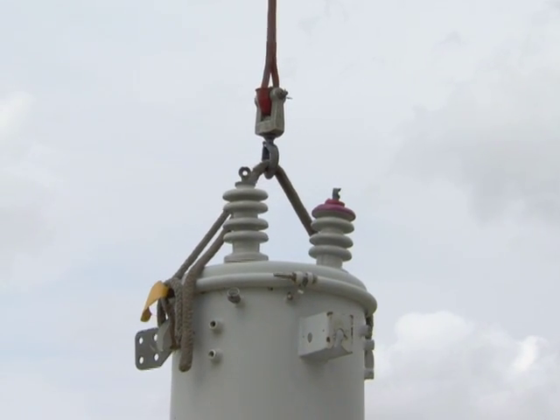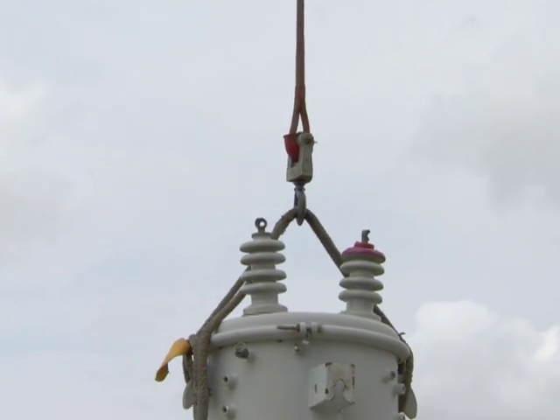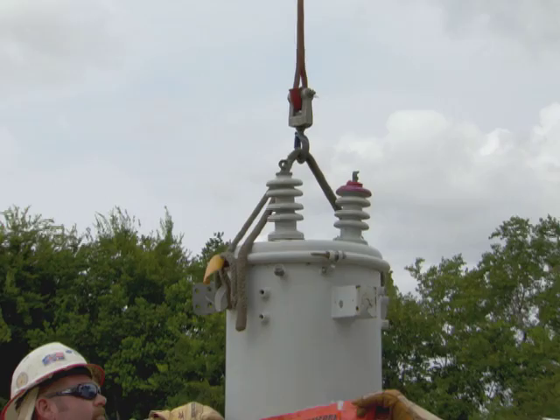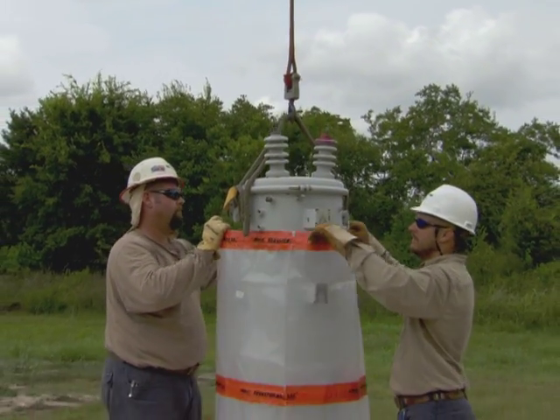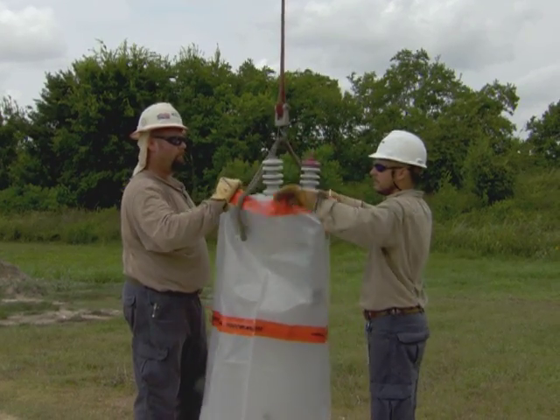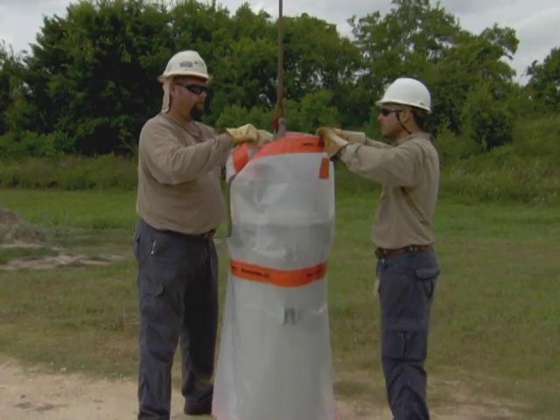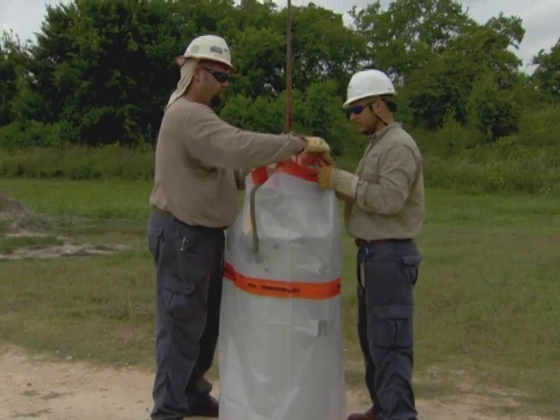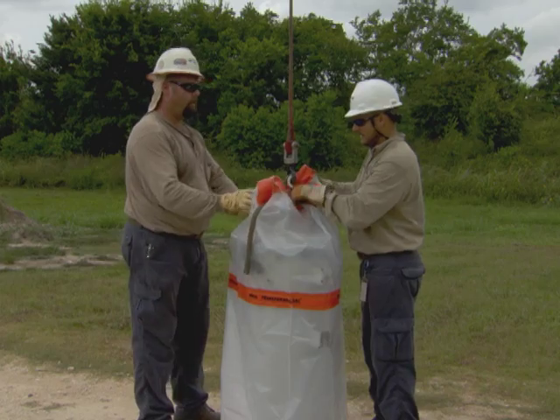Even though CenterPoint Energy, with your help, is working diligently to restore power as quickly as possible, our responsibility to the environment will not be compromised. Oil spills resulting from leaking or damaged transformers, hydraulic leaks, or other sources must be recorded and steps taken to be sure cleanup activities are completed. All leaking transformers must be bagged at the base of the pole to minimize the contaminated area, and the transformer must be picked up at the street for proper disposal. The address of all oil spills must be reported to your coordinator. The coordinator will relay this information to the environmental group, who has the responsibility of notifying the United States Environmental Protection Agency and other applicable environmental agencies.